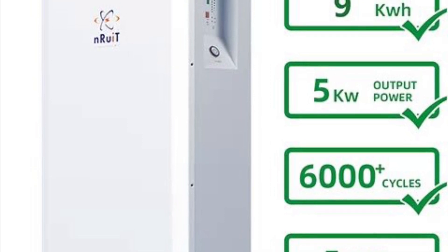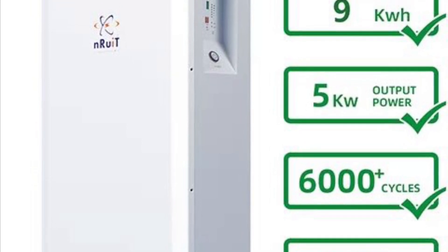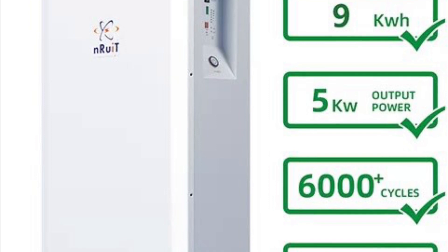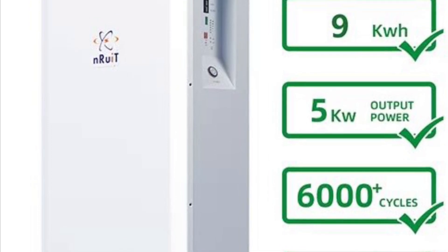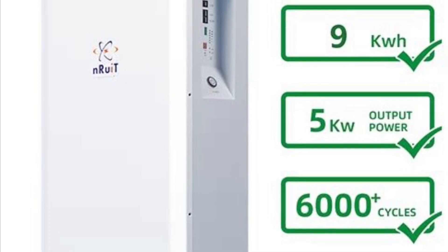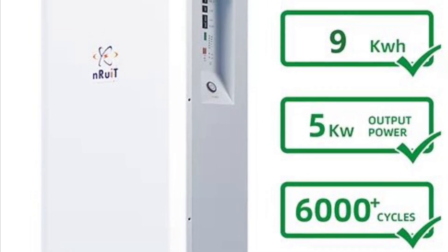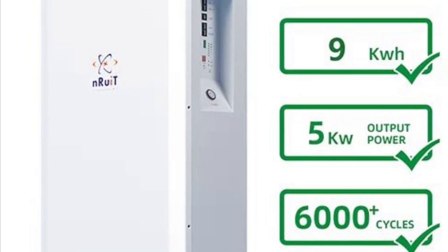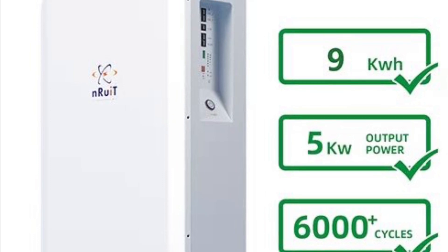Meanwhile, another team was starting to fit the batteries. We have three nine kilowatt hour batteries from a company called nRuiT, and the batteries have a 6000 cycle life based on an 80% depth of discharge. I'm hoping that because we've oversized the system, we will not be stressing the batteries quite as much and so we'll get a longer life out of them.